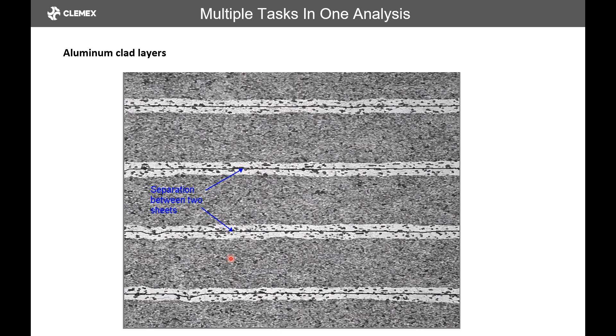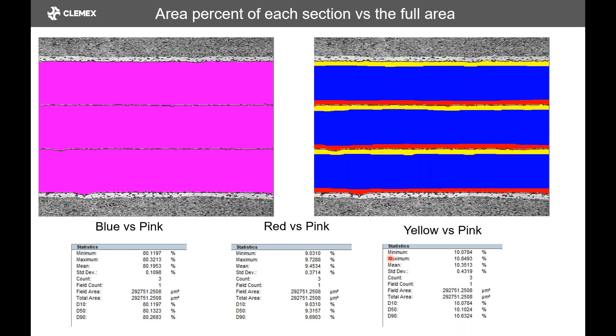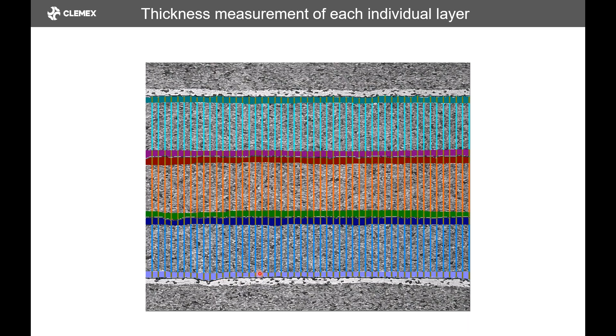And here are our 3 layers that are complete. Then we can measure the top and the bottom layer for each of the pink. So we have a value here, and we have 3 counts. Then we have a distribution in percentage, area percent in this case, of each layer versus the whole strip. And then we can also do the thickness measurement of all the layers, so all the layers are measured individually. And so we have the result that we need. This is what was required at the time for this customer.